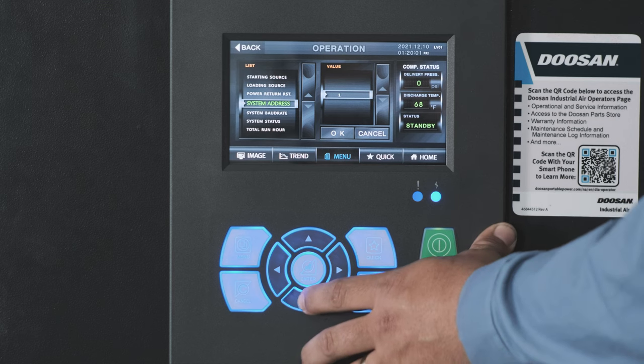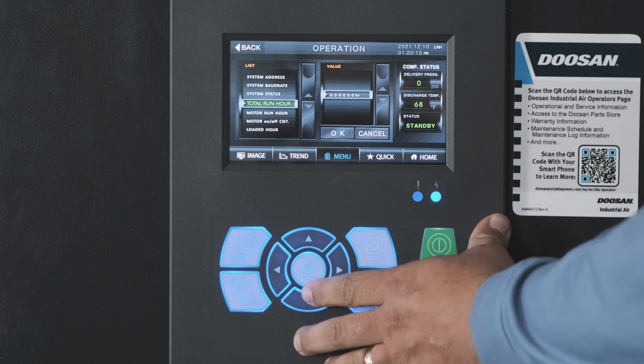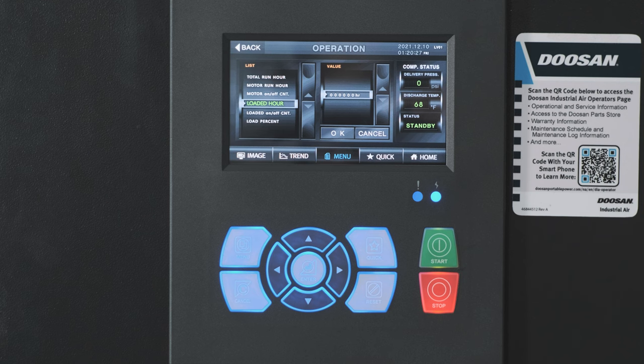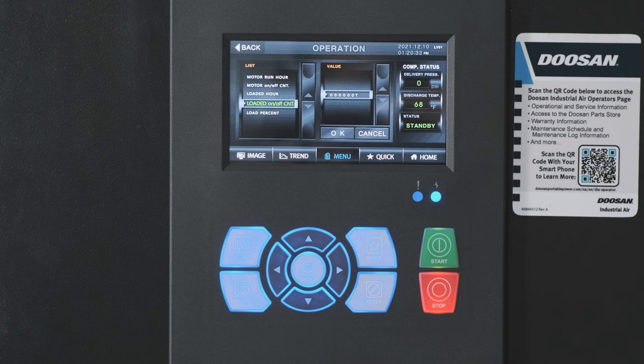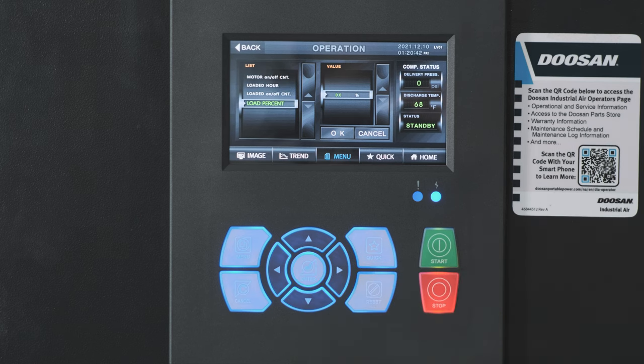Your Modbus settings. Total run hours — these are the hours the compressor is powered on. Motor run hours: when the motor is running, counting both loaded and unloaded times. Motor on/off counter — these are your motor start/stop cycles. Loaded hours: the compressor is actively producing air. Your loaded on/off counter — this is your compressor's load cycles. And load percentage: the percentage of time the compressor is loaded while running.